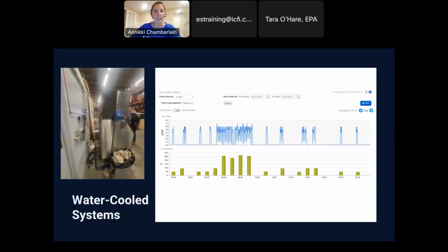So awesome. Here's a quick tutorial on a water-cooled ice machine. This is a high-resolution water signature on the top. This is my gallons per minute, and the x-axis is the time of day. The bottom one is my gallons per hour, right? So this is 1 day. The top one is like the heartbeat, the EKG of the system. This is how a water-cooled system should look.